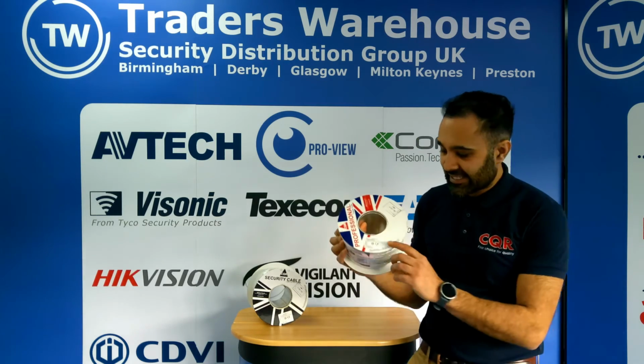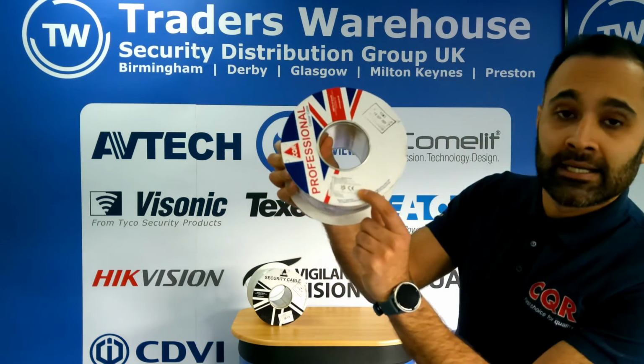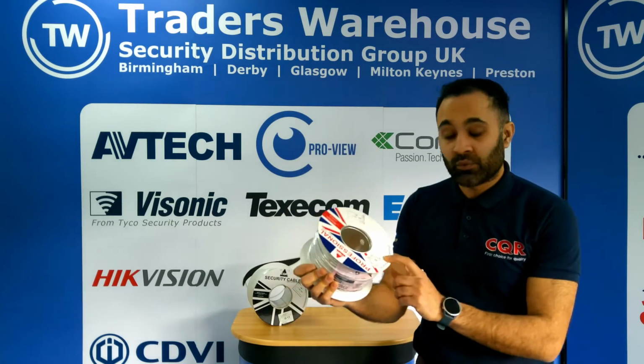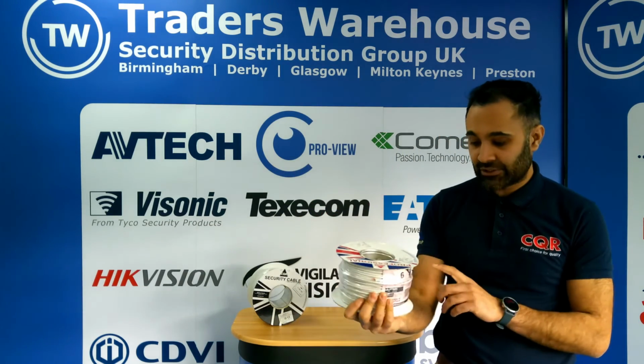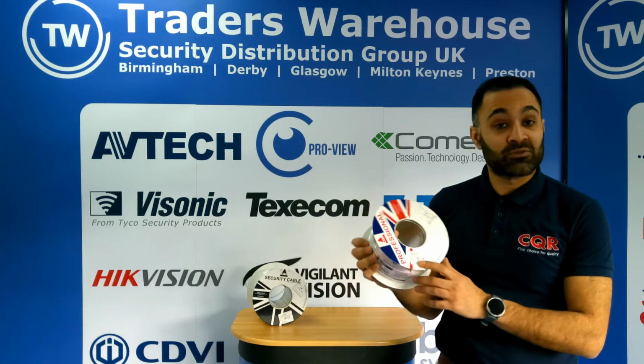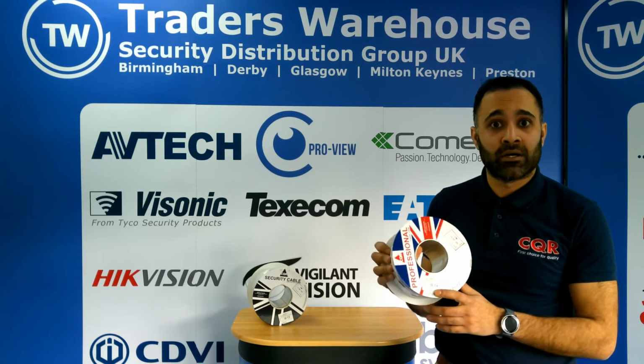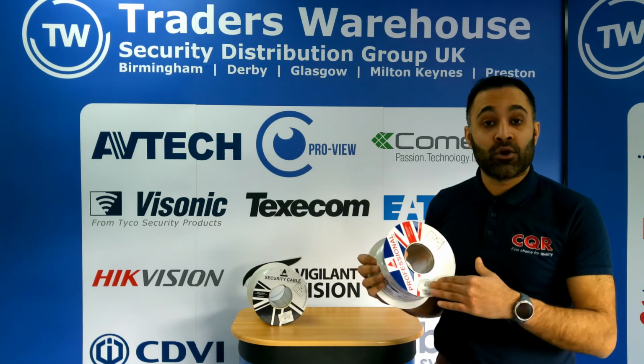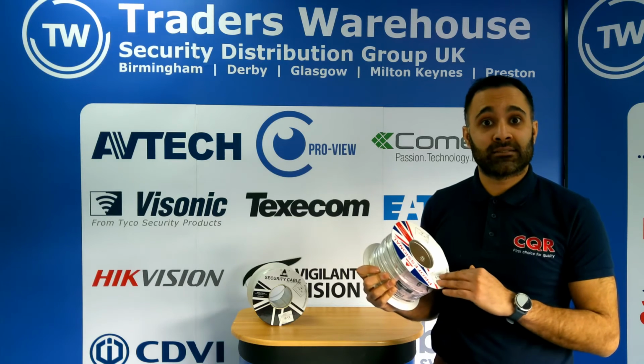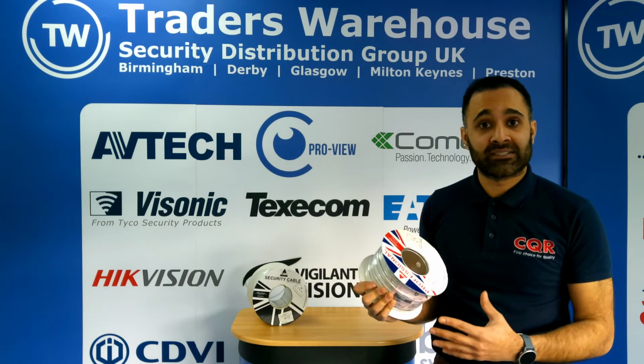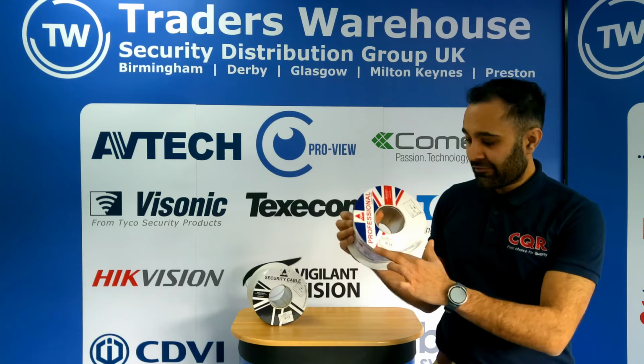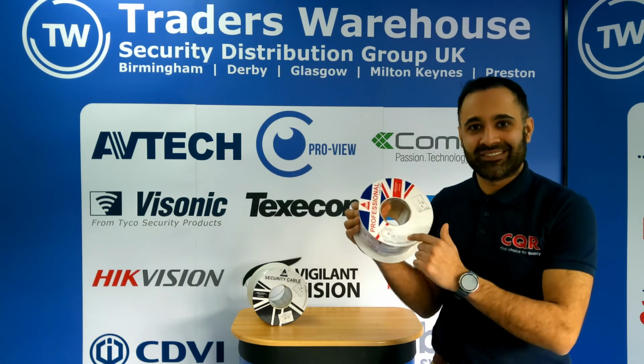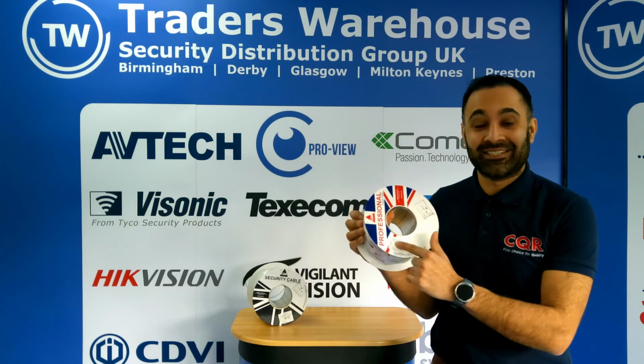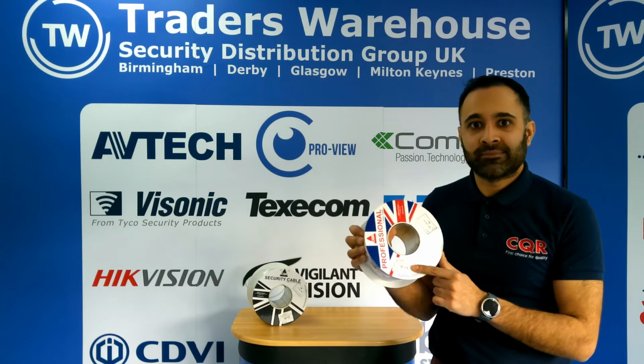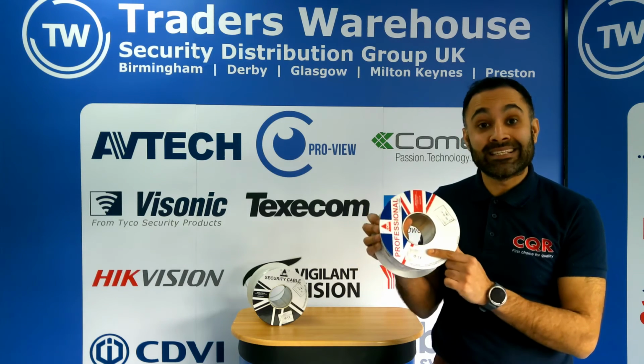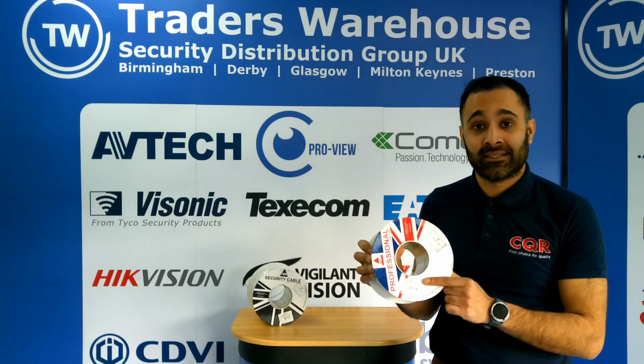It needs to be CE marked, so I don't know if you can see that. Ours are. It needs to say where it was manufactured. So this was manufactured at CQR. It needs to say what level it makes within the CPR standard. If your cable meets all the standards but it doesn't have the information that's on this little label here, it doesn't meet the standard. It needs to say what it is.